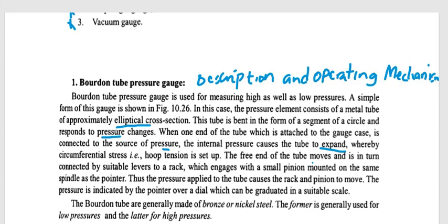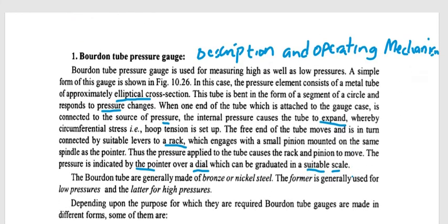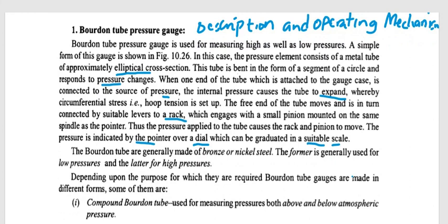The free end of the tube moves and is connected by suitable levers to a rack, which engages with a small pinion mounted on the same spindle as the pointer. Thus the pressure applied to the tube causes the rack and pinion to move. The pressure is indicated by the pointer over the dial, which can be graduated in a suitable scale and the pressure can be read and recorded. A Bourdon tube is generally made of bronze or nickel steel.